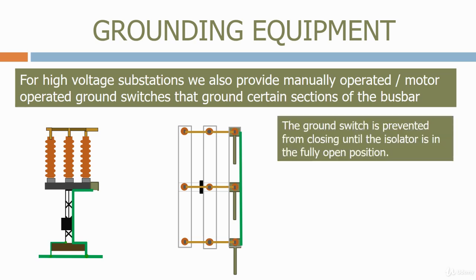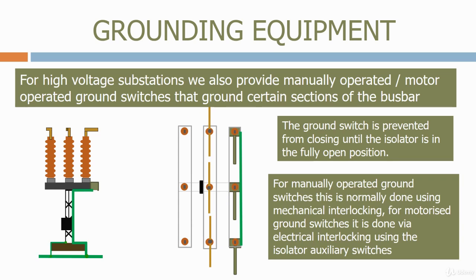The ground switch is prevented from closing until the isolator is in a fully open position. For manually operated ground switches, this is normally done using mechanical interlocking. For motorized ground switches, it is done via electrical interlocking, using the isolator auxiliary switches. We will look at interlocking in more detail in part 2 of this course. Let's now close the ground switch.